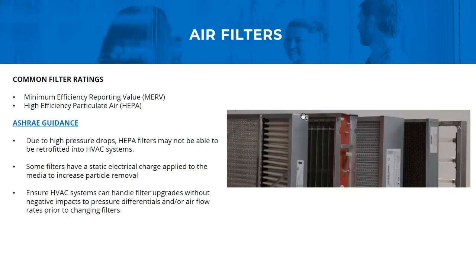Yeah, great. Thanks, Katie. Lastly, filters have been a huge discussion of ours, as well as, as Katie mentioned, the CDC, ASHRAE, EPA. ASHRAE's current recommendation is to increase a filter to a MERV 13 or higher. The MERV rating specifically stands for minimum efficiency reporting value. High efficiency particulate filters are what are better known as HEPA filters. Those are typically what you would see in a hospital setting, surgery room. Due to the high pressure drops with HEPA filters, most office complexes are not able to achieve or retrofit an HVAC system with that type of filter.